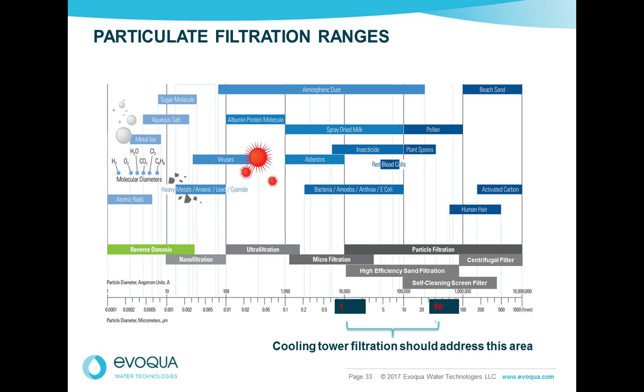Now, this is a kind of a busy chart, but it shows you various particles from large to very small. The point here is that, generally speaking, in a cooling system, your primary concern is that 1 to 50 micron range. In some cases, it may be 1 to 100. Depends on the conditions. So you should choose a filter that's efficient in that range.